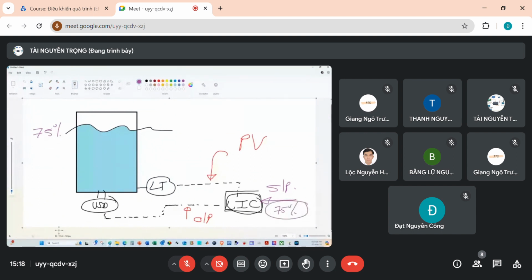Now, as I measure the value out in the tank, my process controller responds accordingly. If I measure a value of 73%, the controller knows I am below the target value, and it will send a signal to the variable speed drive to slow down just a little bit. As the variable speed drive slows down, the level rises and gets close to the set point.